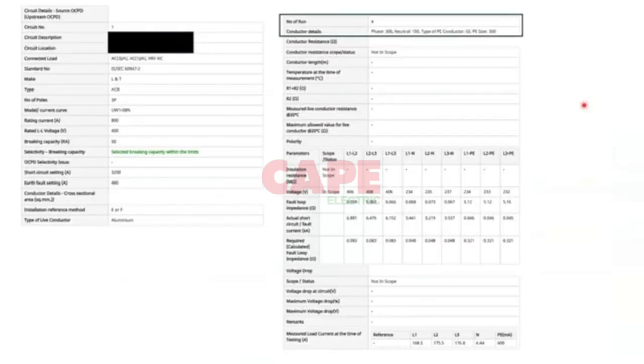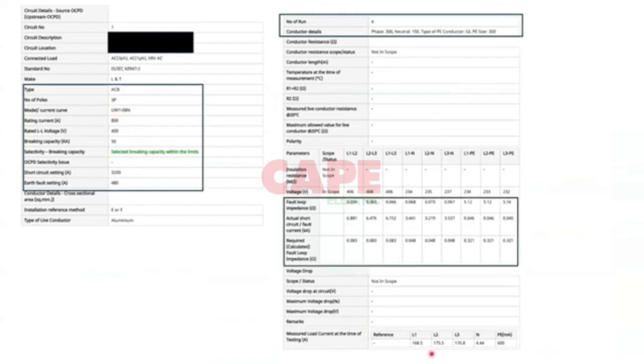The other one is an example where you can see clearly that the conductor is 300 CSA, 3.5 core, and they have run 4 runs of it, and then there is this ACB of L&T make. When you come to the actual load current, the fault loop impedance is all matching. But if you come to the actual load current, again it is very high. Again, in the protective earth 600 milliamps of current is flowing. I don't know if that is very dangerous. That is very much dangerous. But the load current is also very, very much less.